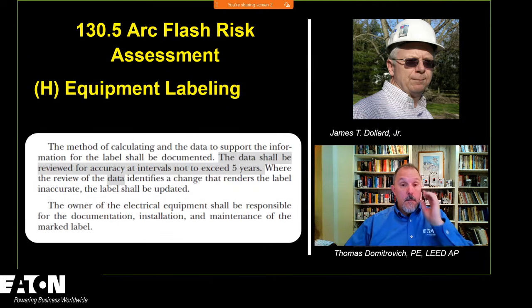We could also have a change on the utility side, like the utility changing transformers directly upstream of where we're at. Within the facility, I could have a 1200 amp electronic trip molded case circuit breaker fail, and I replace it but couldn't get the exact same device, so I got something close. You're going to have to look at all the data in your study to see if that impacts your incident energy analysis.